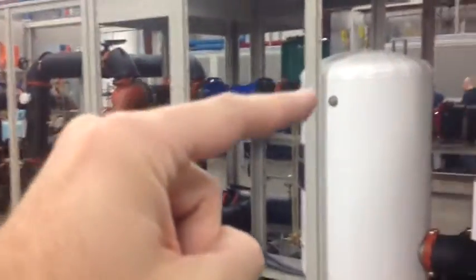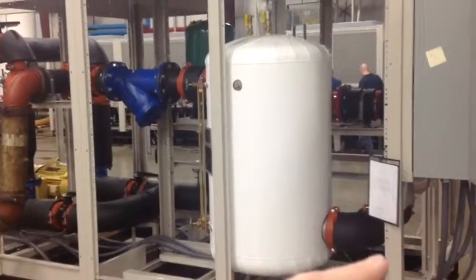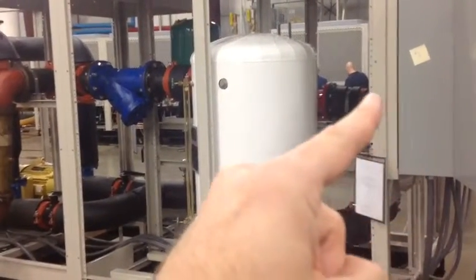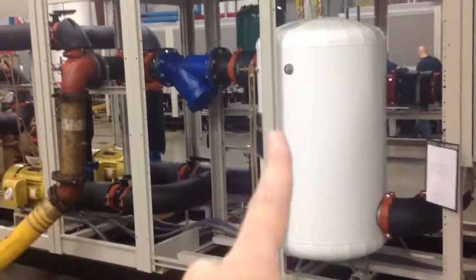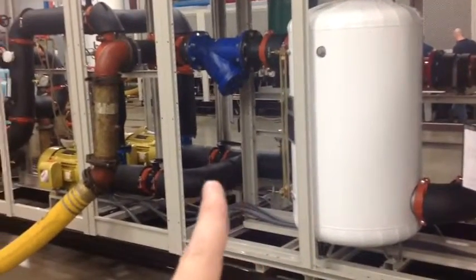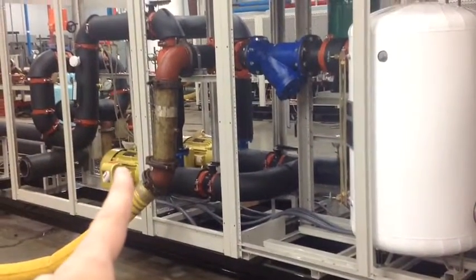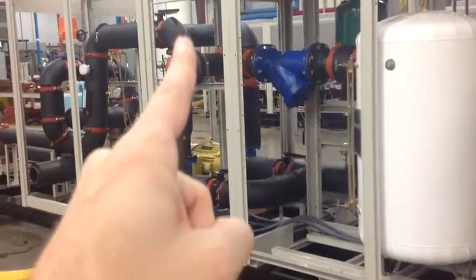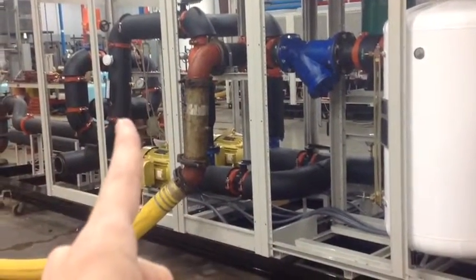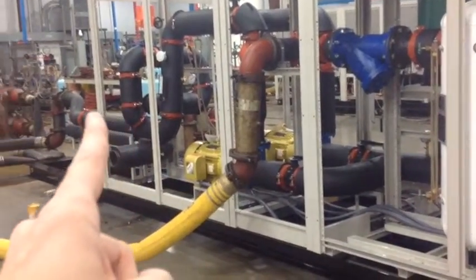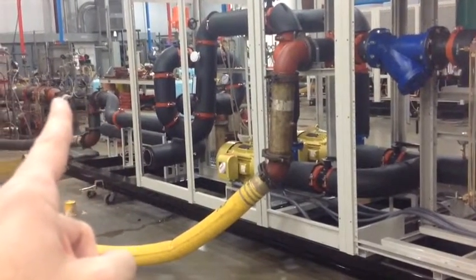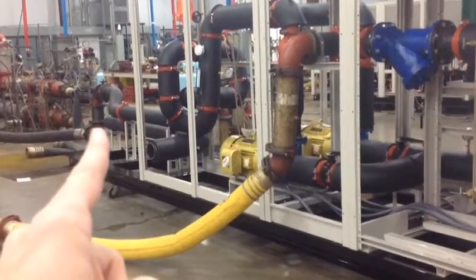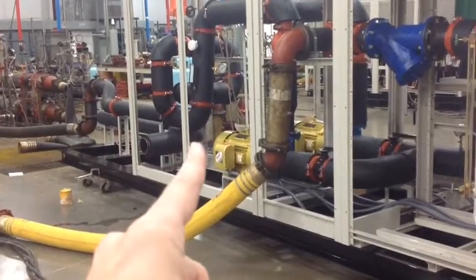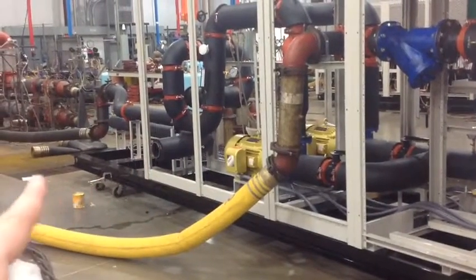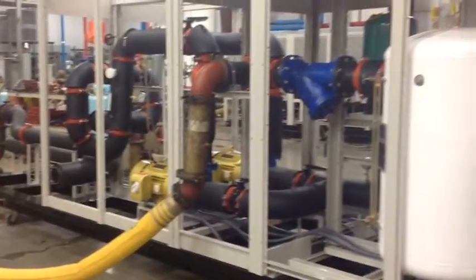Let's take that tour one more time. Through the strainer, down through the tank, around and through the air separator, down and into the pump suction, through the isolation valves, then vertically up through the pump discharge, and down and over into the portion that goes through the future free cool area, up into the mechanical modules, back through the lower header of the mechanical modules, and ultimately out to supply chilled water to the building.